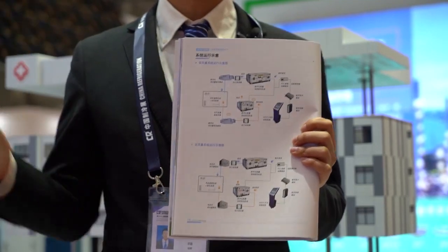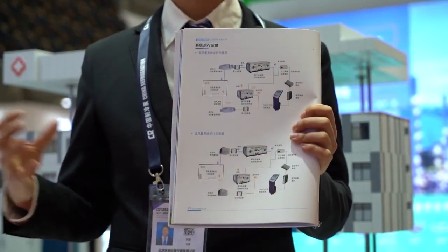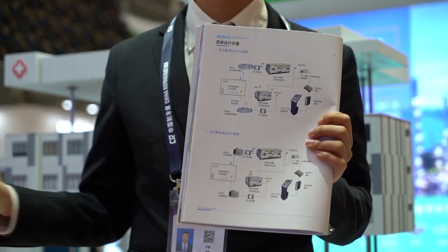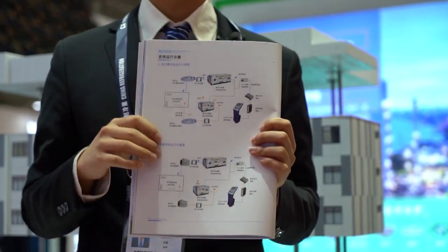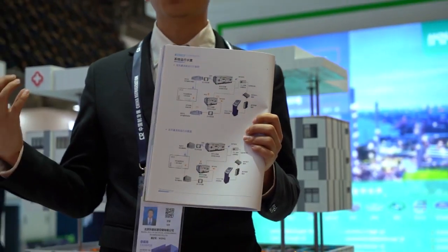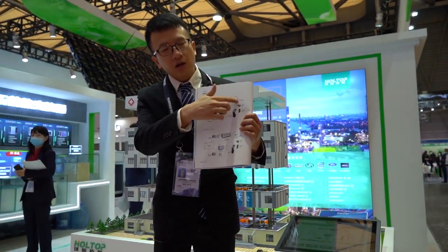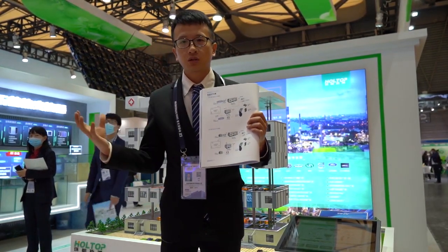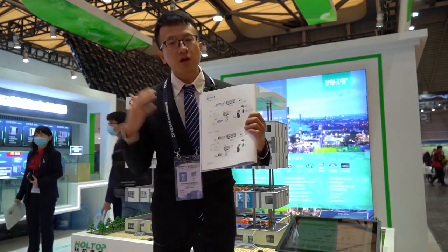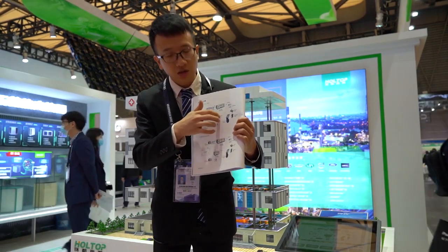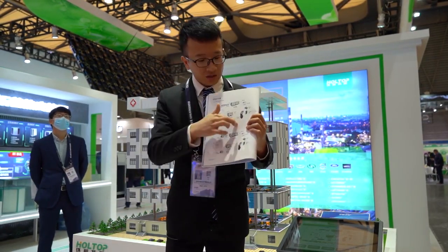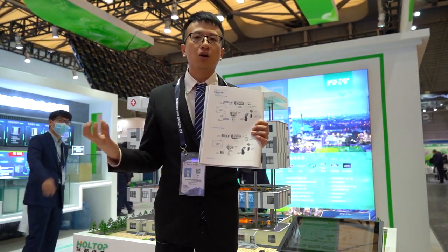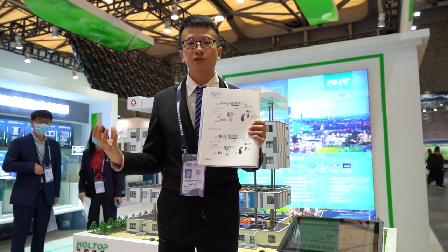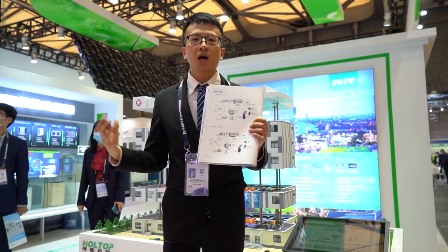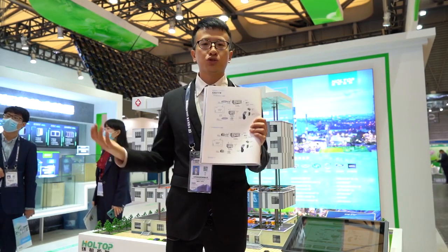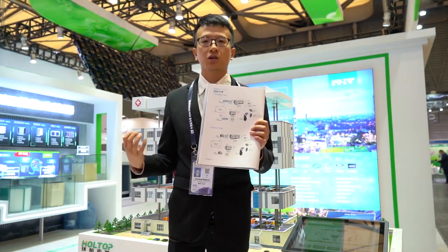Next is the variable airflow modular. This modular is to sense parameters such as fresh air flow and the CO2 amount, and to sense the temperature and the humidity. And the fresh air goes through the AHU, then is sent into each room inside the hospital, and then part of the fresh air will circulate and return to the exhausting air unit. The purpose of this unit is to recycle and recover part of the energy from the recirculation air, and of course, at the same time to exhaust some of the air to the outside to ensure the room has the correct and suitable amount of air changes.